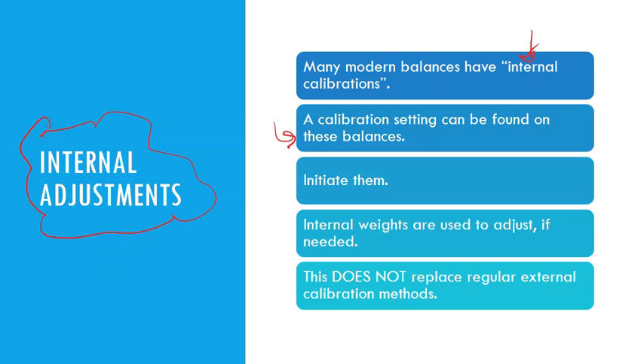So a calibration menu option will show up on these balances. Very easy to perform. As a user, I go into that menu, I choose internal calibration or calibration, and then there's a self-check mechanism in the balance. It knows that something is supposed to mass a certain way, and then it double checks itself, and then it will finally adjust the mechanism that gives you that display readout until that number matches what that standard calibration weight is supposed to be. So you initiate it on the touch screen of the balance. After that, internal weights are going to be used to cross-reference those values, and then it will self-check itself. It will probably display OK or give you a confirmation that the internal calibration check is now finished.